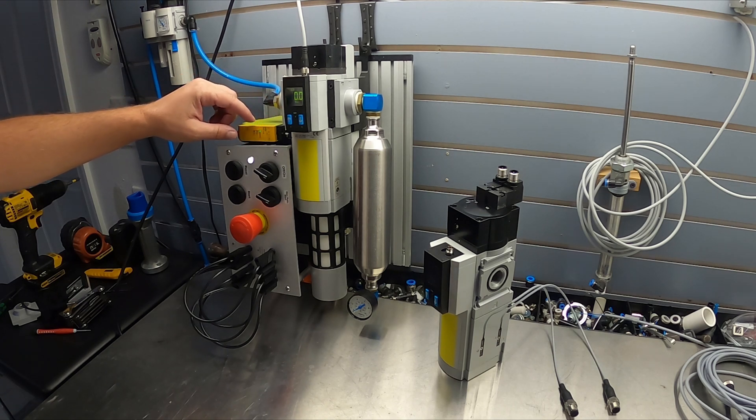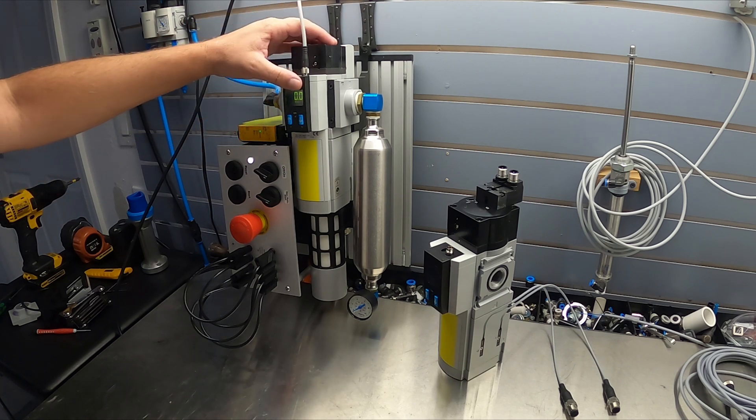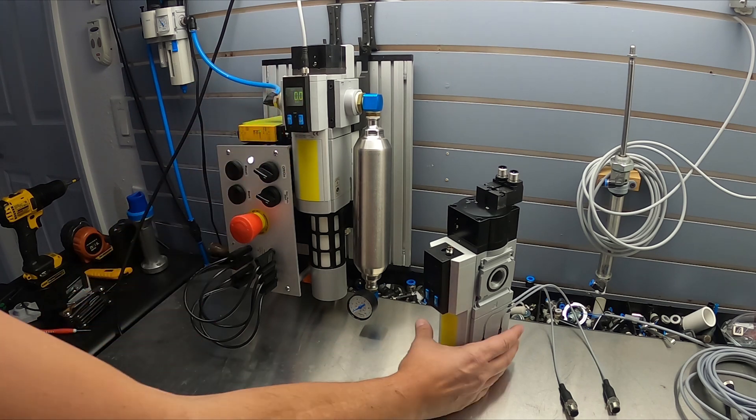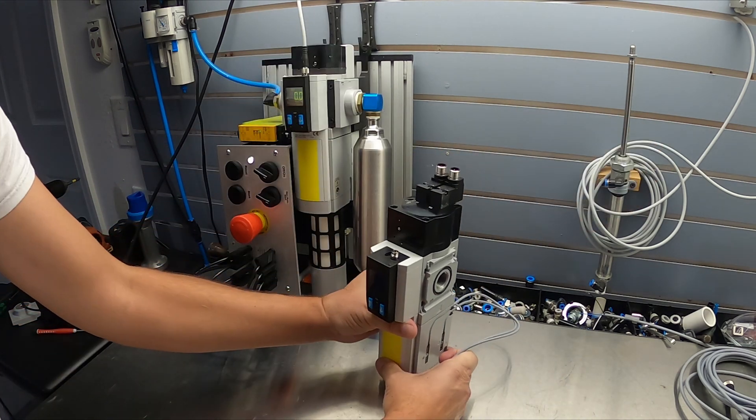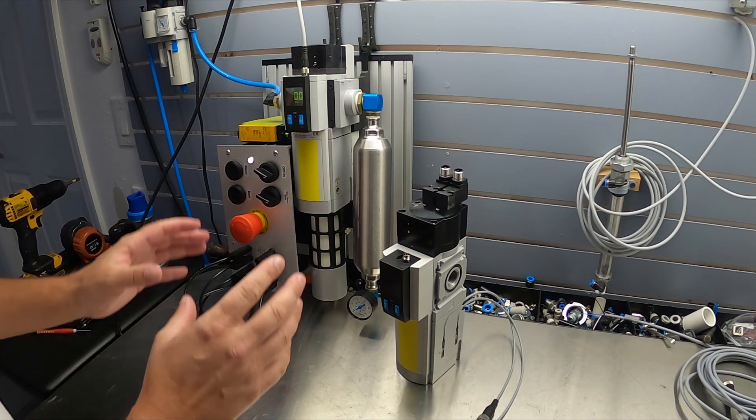So this does a self-check and this does a self-check. And that self-check logic is built into the device, whereas with this one that self-check logic would have to be done at the control panel. That is the biggest difference between the two.